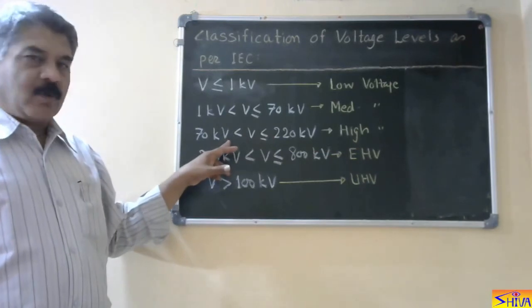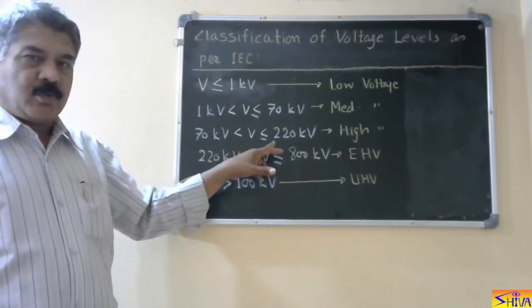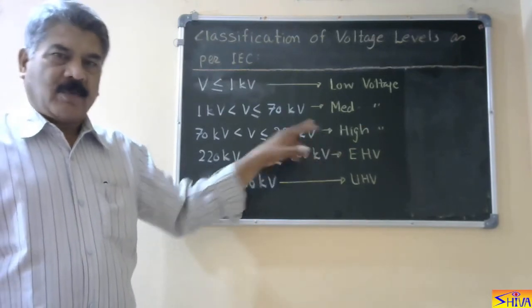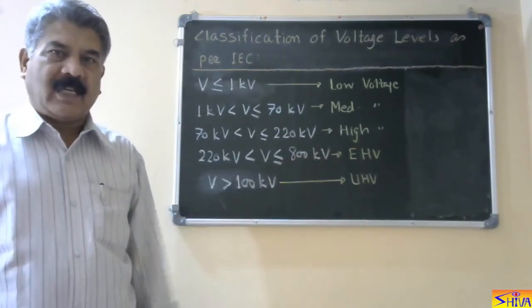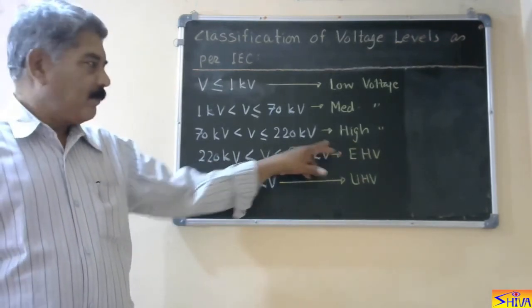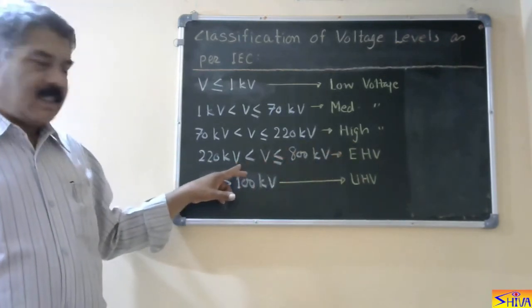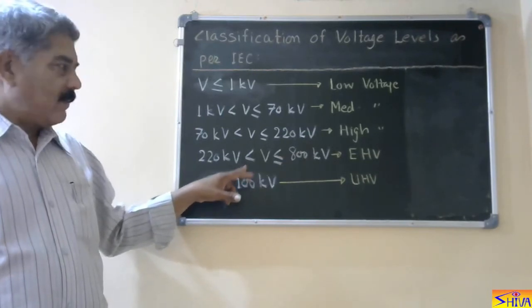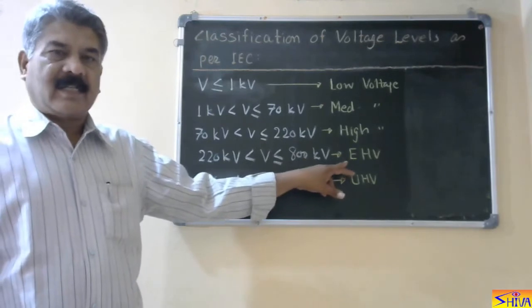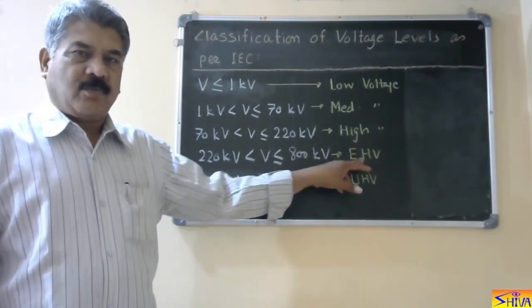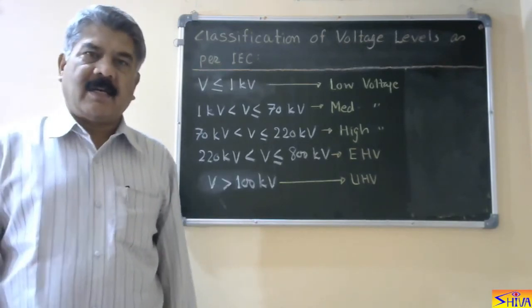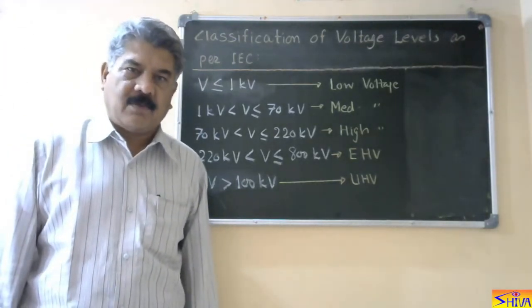If voltage is more than 70 kV but less than or equal to 220 kV, it is high voltage. So 132 kV and 220 kV lines come under the high voltage category. If voltage is more than 220 kV but less than or equal to 800 kV, it is extra high voltage. The 400 kV and 765 kV lines come under extra high voltage.